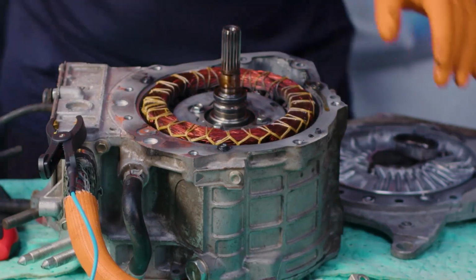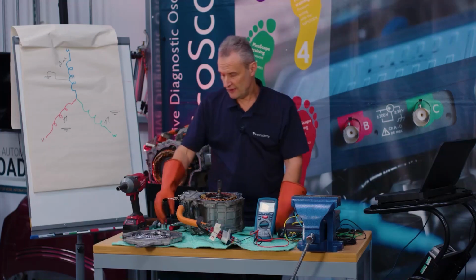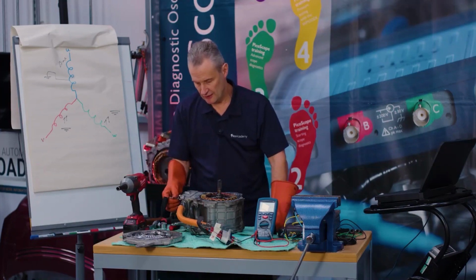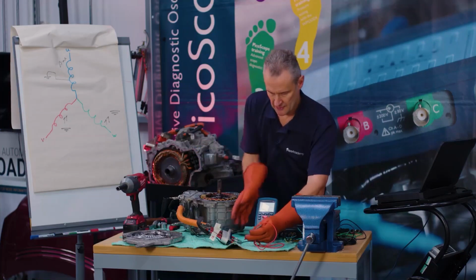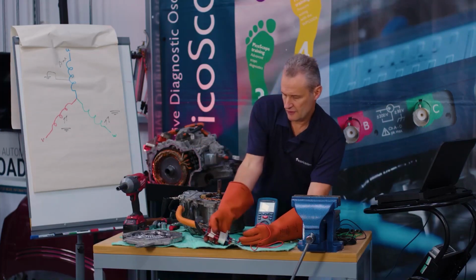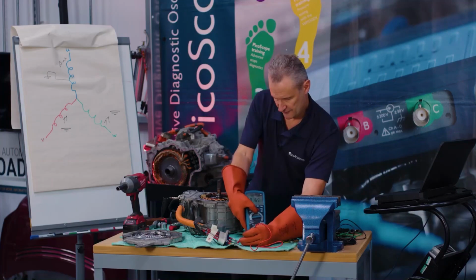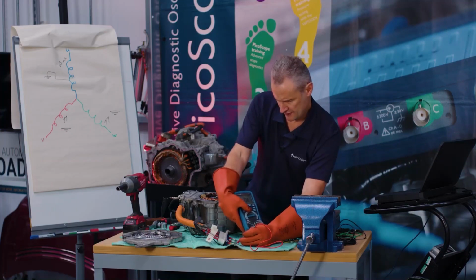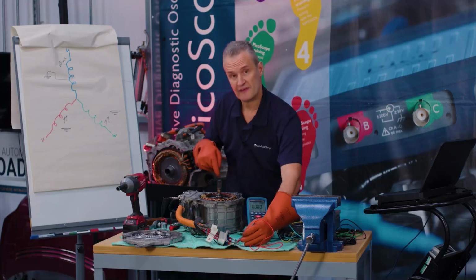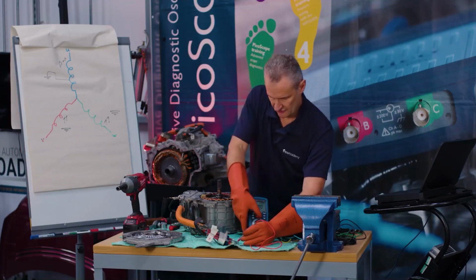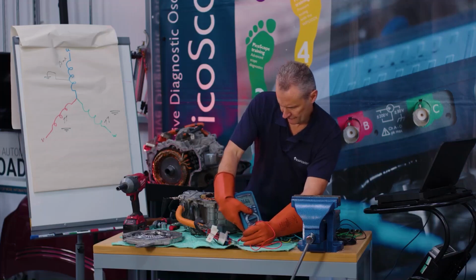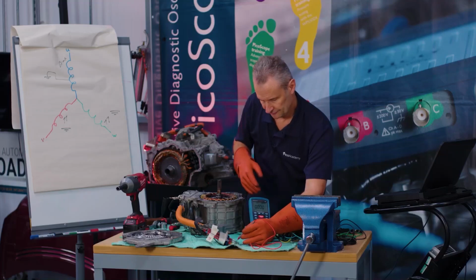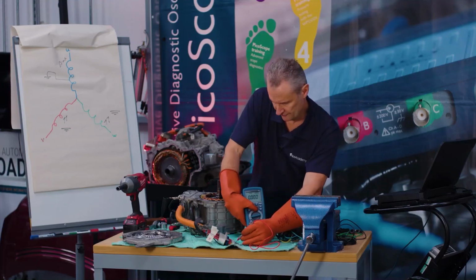Okay, so we've now got our insulation meter back on, measuring reference to the ground here. We'll go on to the U phase, press the test button. Okay, our test voltage, now we still have a short through there. So I was hoping that that had moved it. Maybe there's still some debris left in there. Let's go to the V phase. No, still a short to ground. Finally, the W phase.